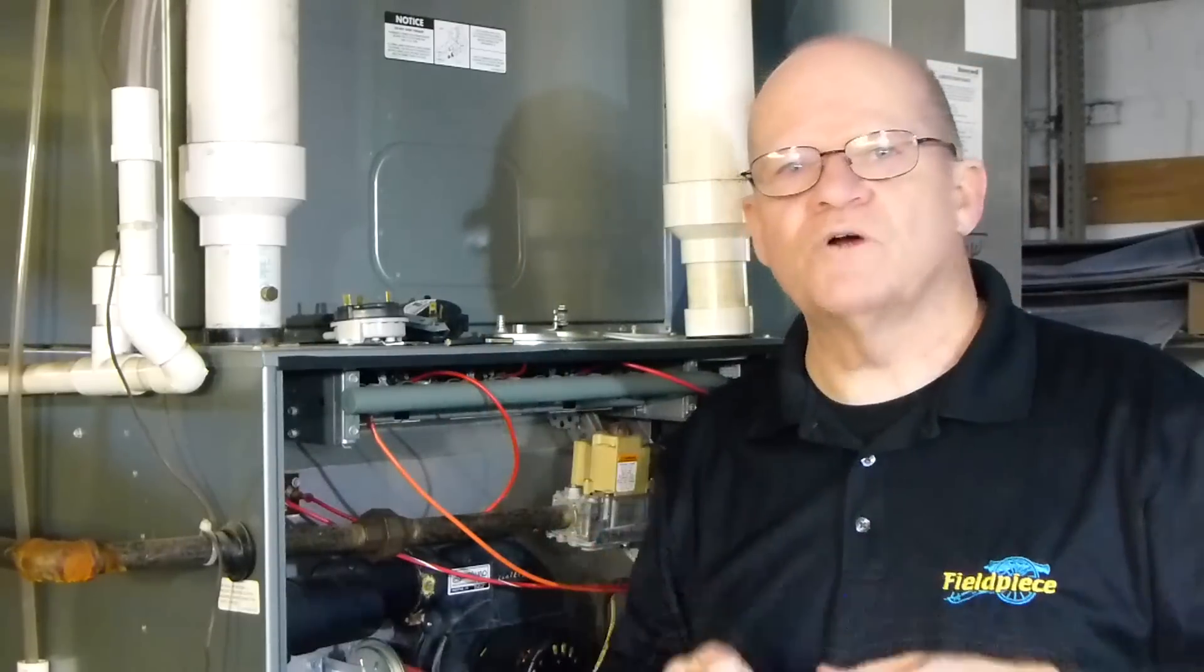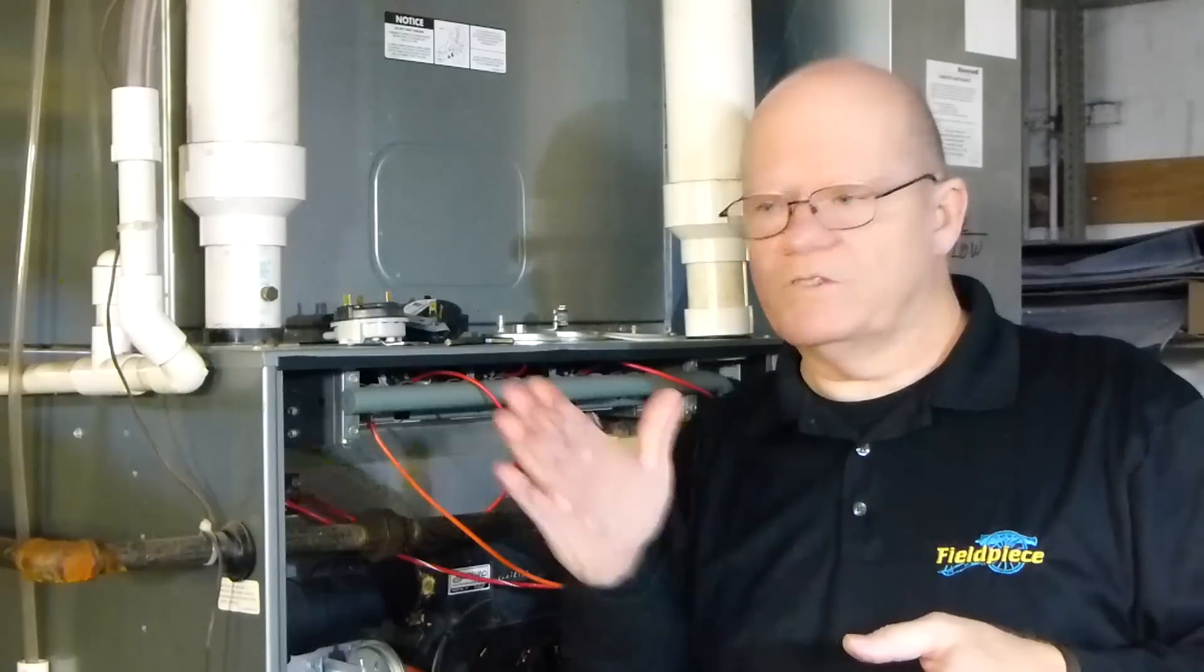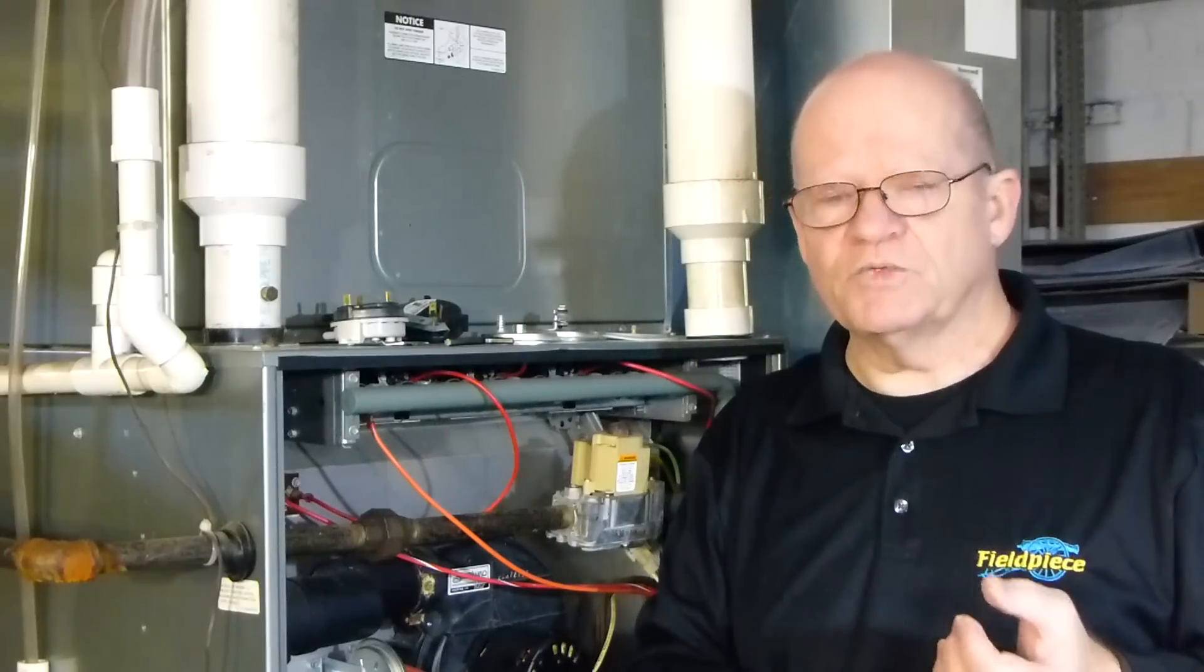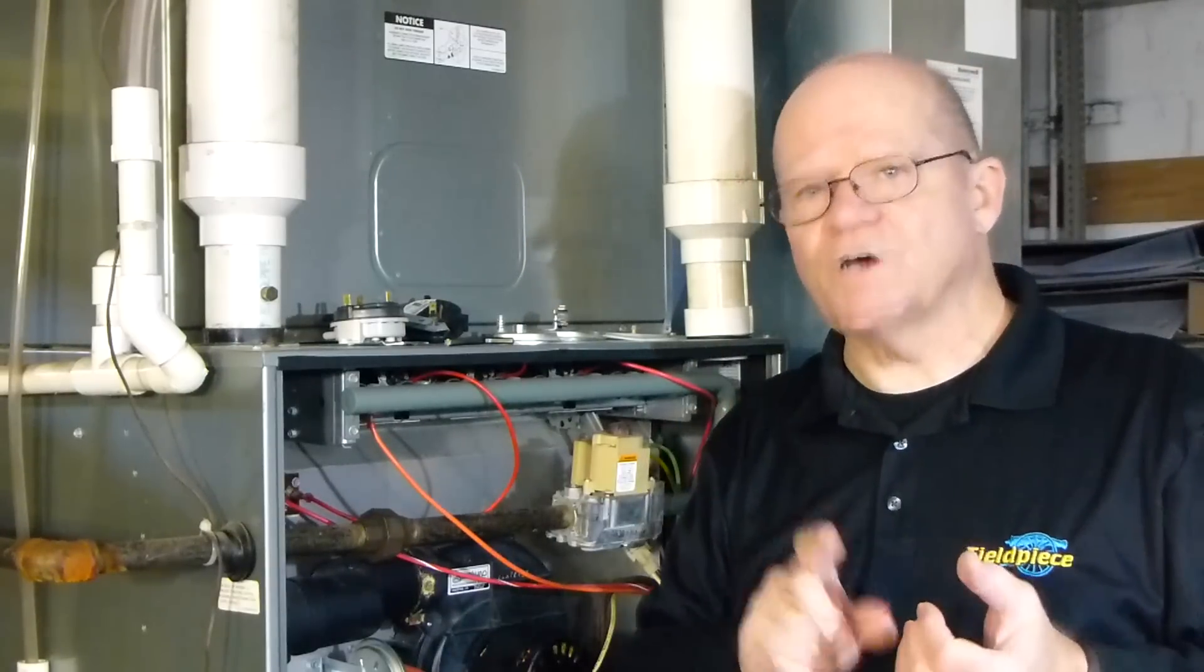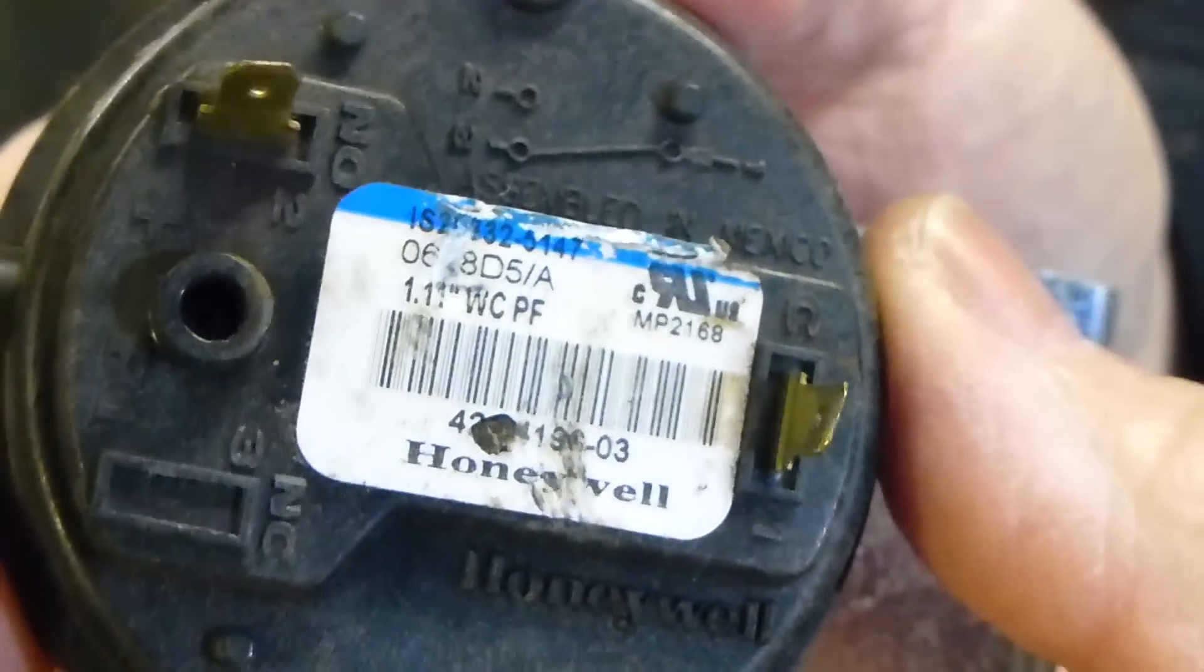What that does is, if one is creating more pressure or draft than the other, it's going to make that pressure switch bellow. So it's going to go one way or the other and it's going to shut that furnace down. Like I said, the purpose of the pressure switch is to shut the furnace off. That's important that you know that.